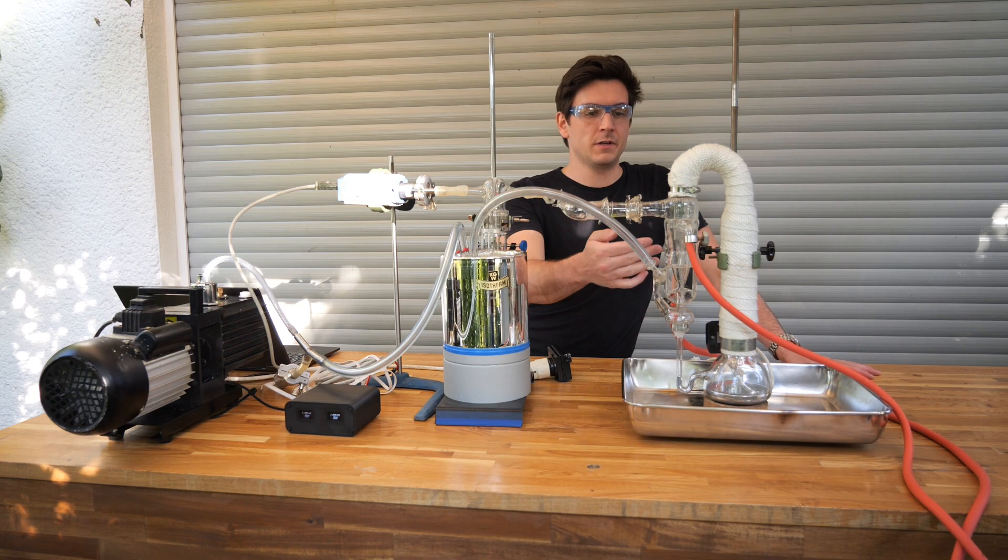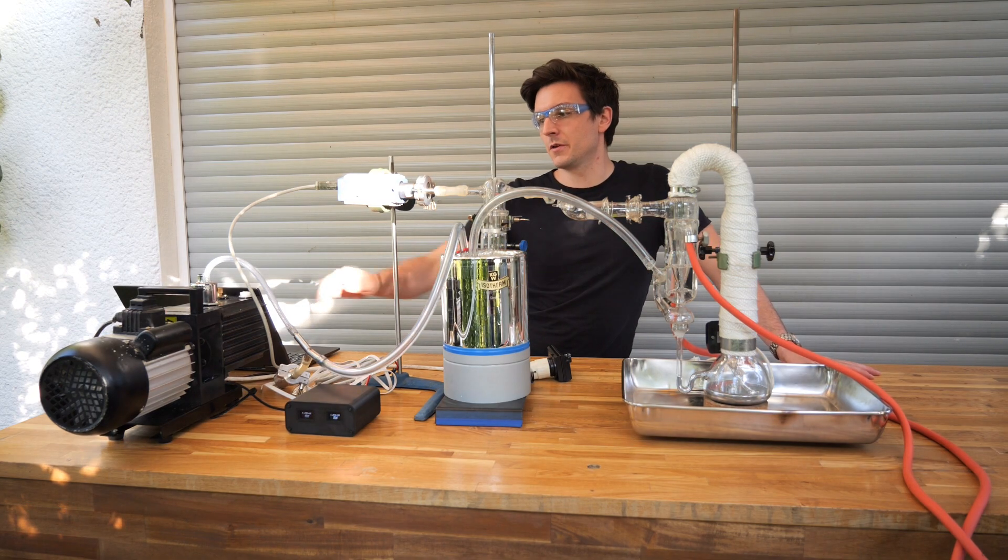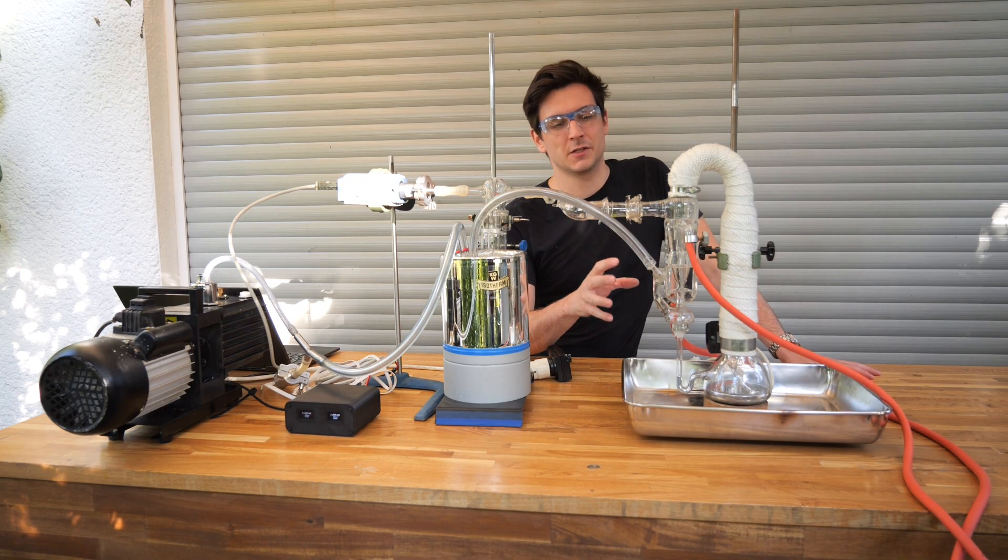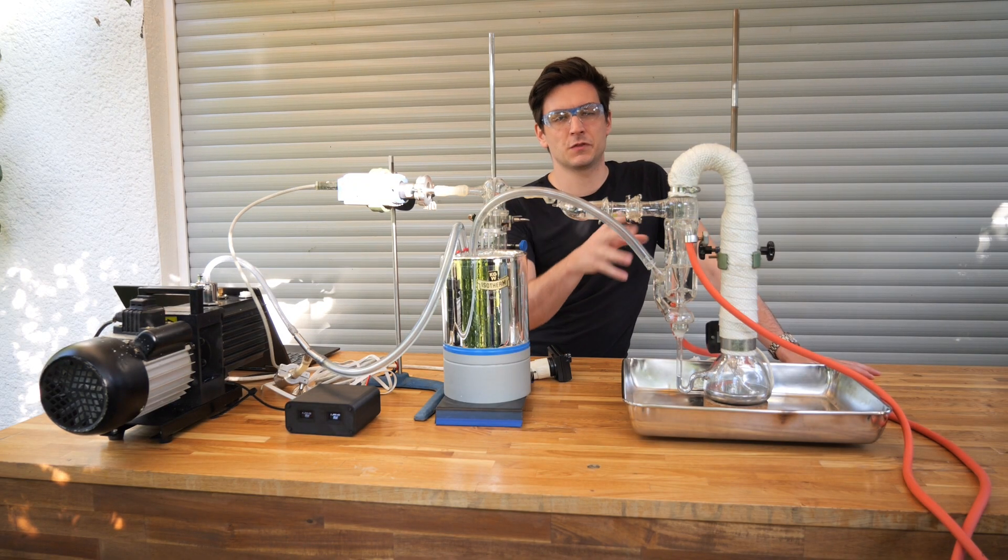Before we can turn on the diffusion pump we have to turn on the roughing pump to pump the system down. The diffusion pump would basically not work at atmospheric pressure.